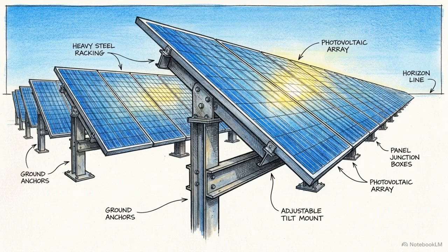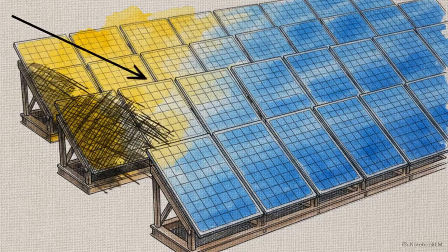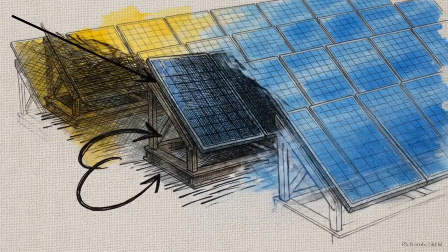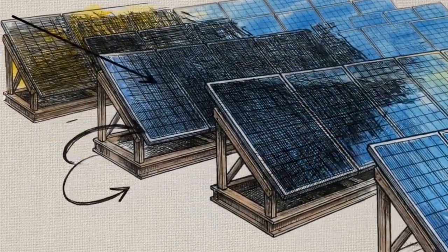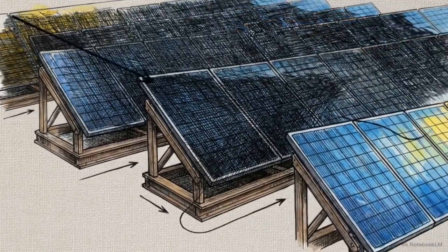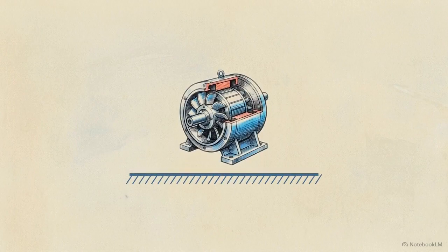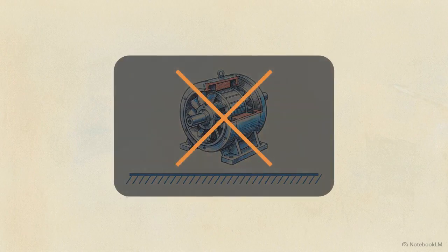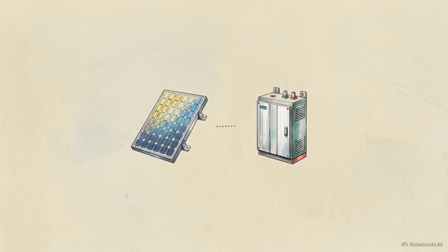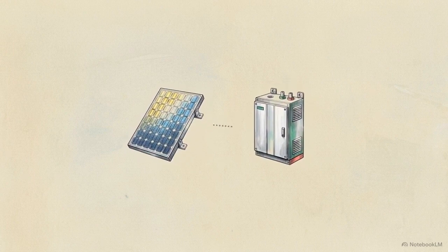Look at a sprawling solar array on a clear day, and it seems like a highly reliable power source. But when a sudden cloud cover rolls in, that generation profile drops instantly. Traditional power grids rely on the massive physical momentum of spinning mechanical turbines to ride out these sudden drops. Transitioning to a renewable microgrid strips away that heavy mechanical inertia, leaving the local system highly reactive to the environment.